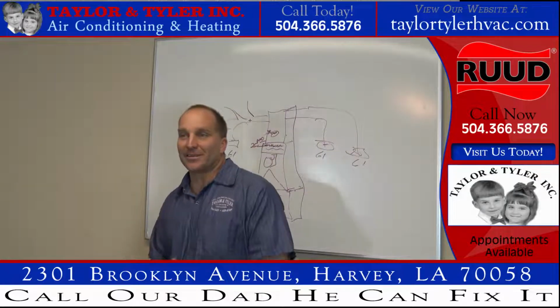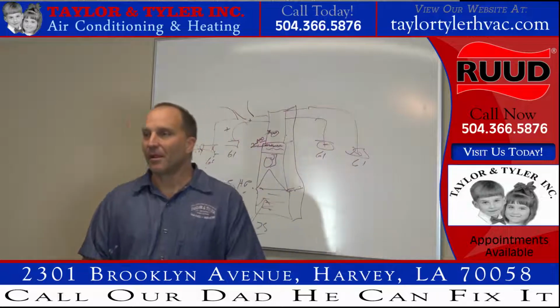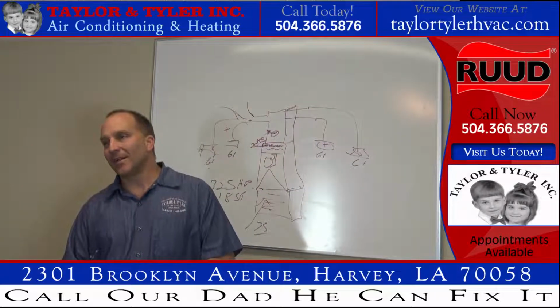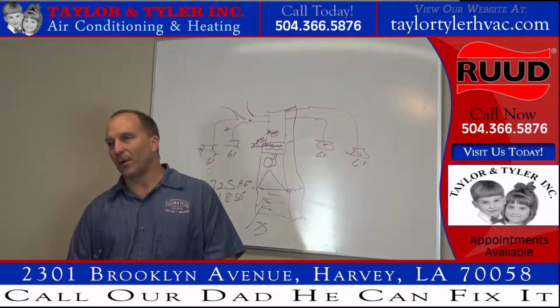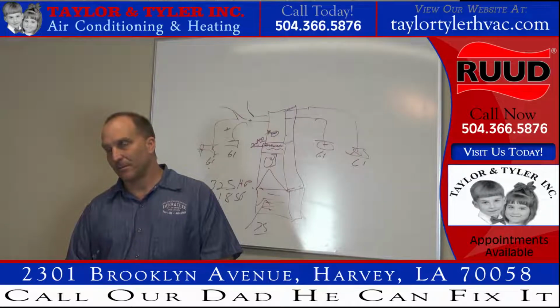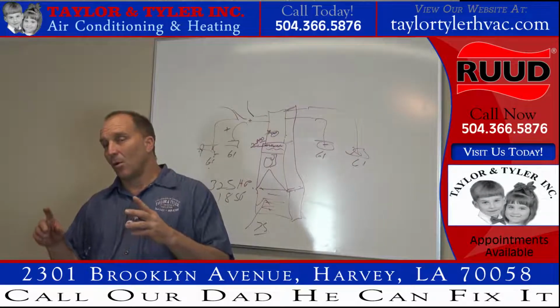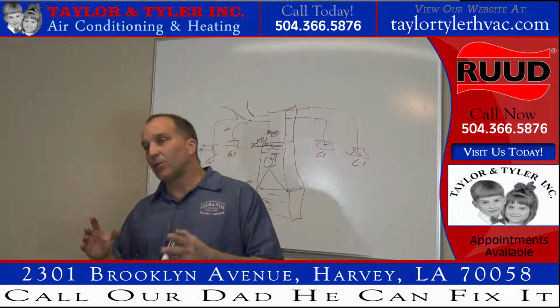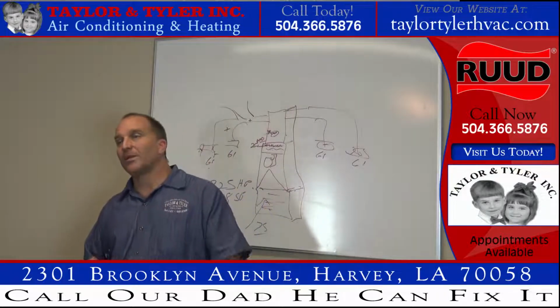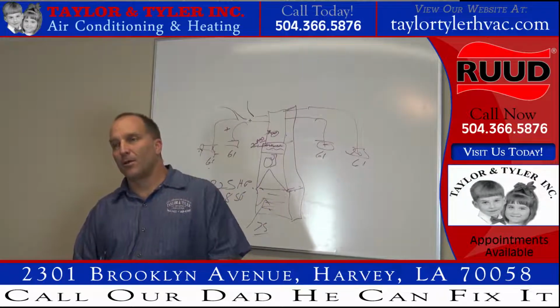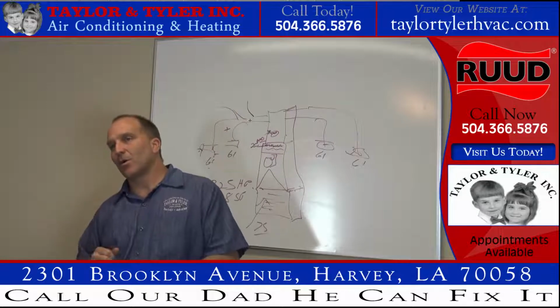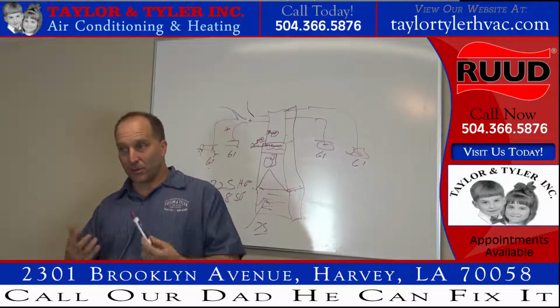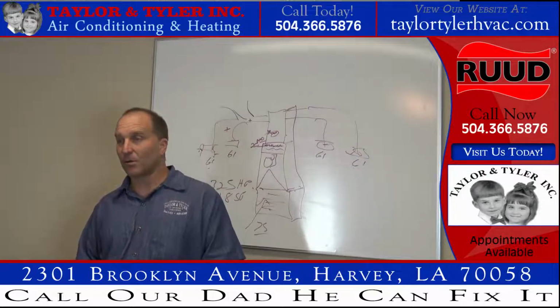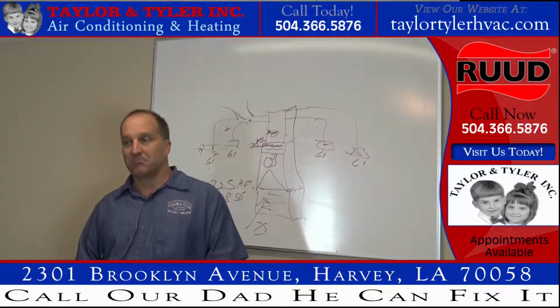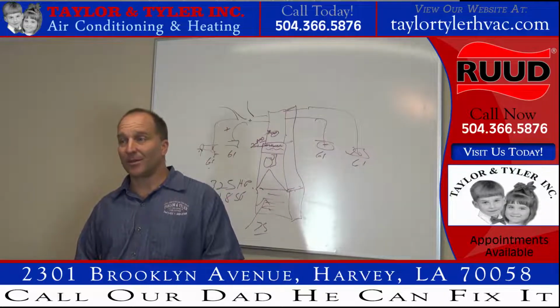So here's the case. You have a 3-ton condenser and a 2-ton evaporator coil. And you go, Eric, I can't figure out what's going on with the system. Well, I'm assuming you checked to make sure that the model numbers are proper. They're not. You've got a 2-ton coil and a 3-ton condenser.